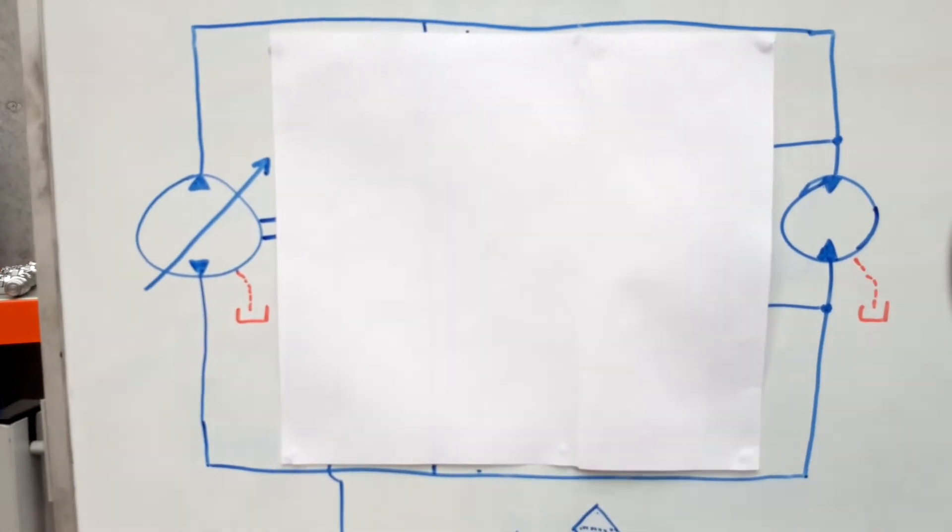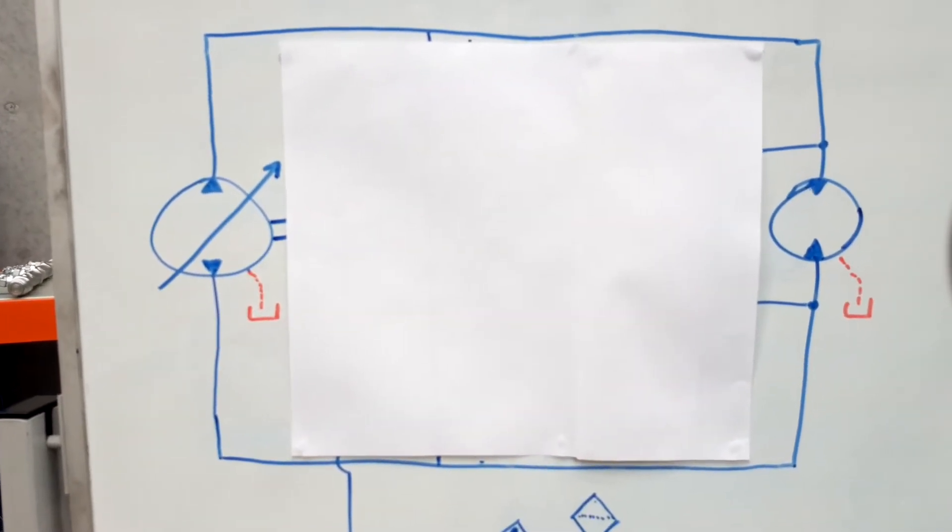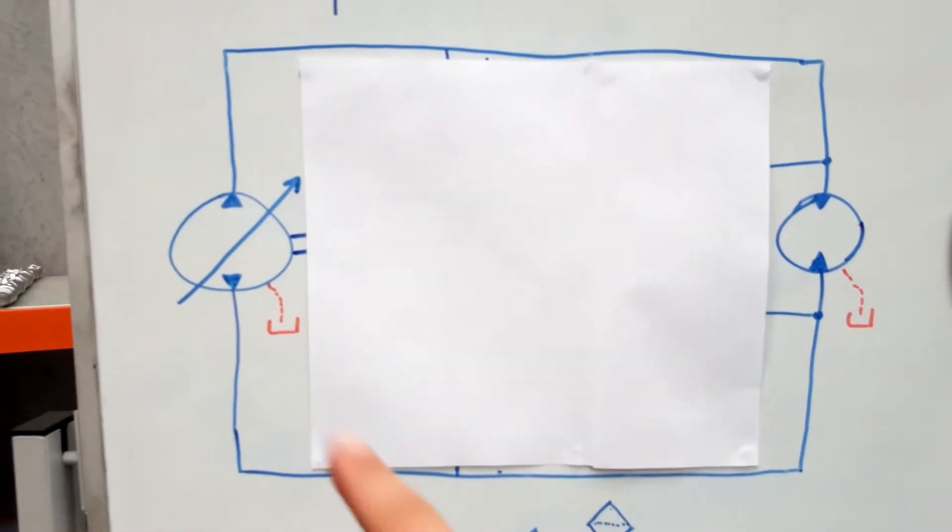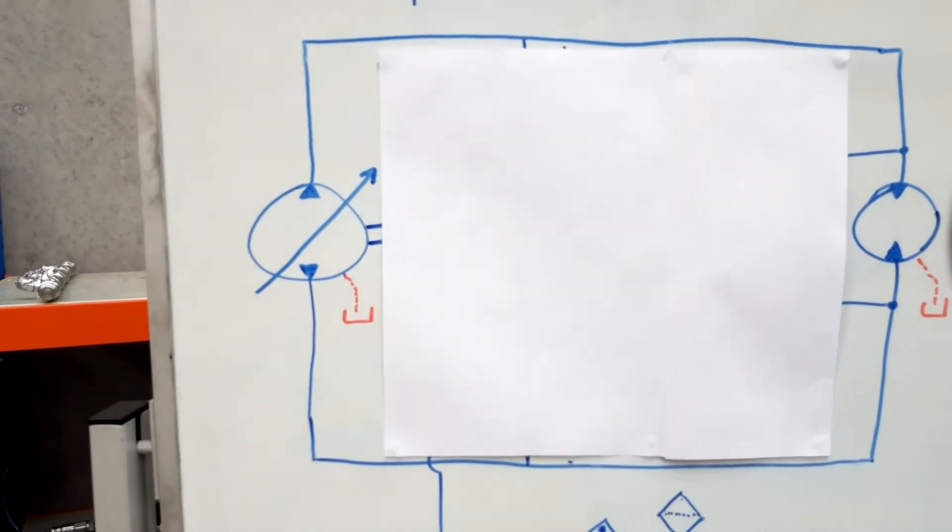This is good - we can control it. There's no extra valves in there to create heat in the circuit. The idea being that we have good control, forward and reverse, just by operating the swash plate, either manually or using a pilot circuit.